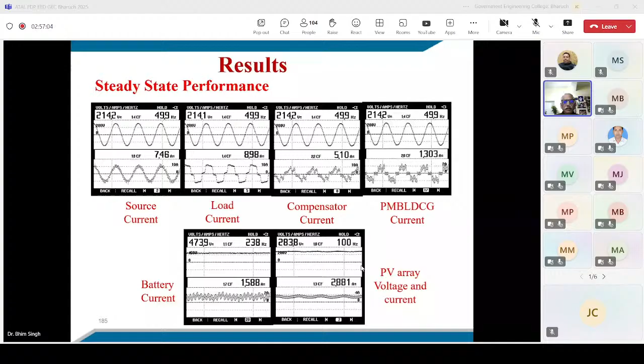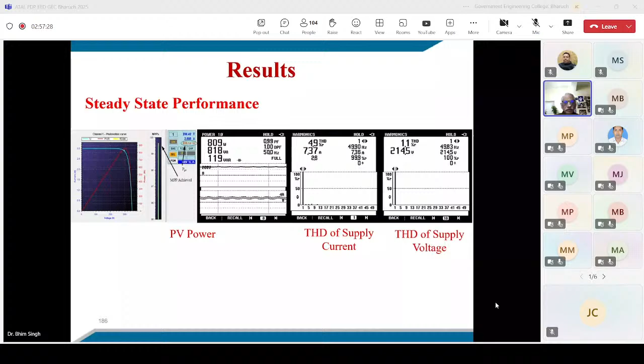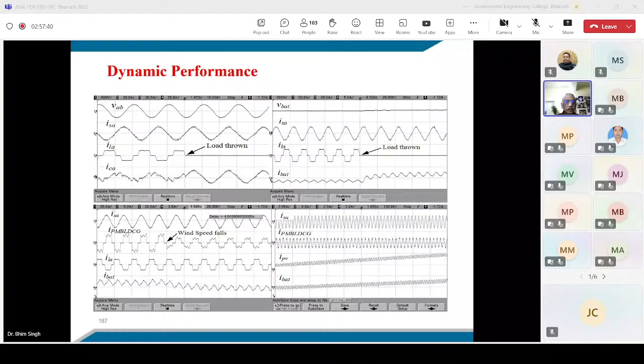We also worked out that we force this machine, especially brushless machines, either squirrel cage or synchronous machine, to operate at an unsaturated condition by reducing the voltage. If you operate without a converter, just with a capacitor, they may be unstable. But with the converter and closed loop control, we are able to make this unstable system stable through proper control. You can see the performance during load removal - it does not affect the generator current because it was driven typically from the DG set or hydraulic source, and the induction motor starting was not possible before. But when we put the converter in, it's able to start successfully without any problem.